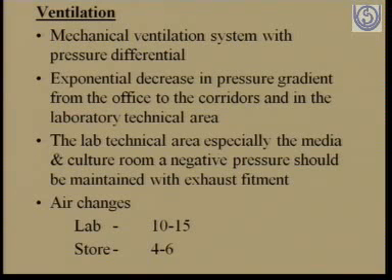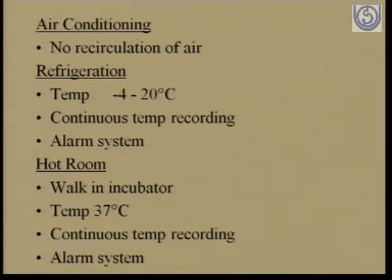Ventilation is a very important requirement because of the nature of the work, especially the microbiology work, where you need a separate air handling unit for the microbiology area so that the possibility of mixing of air can be avoided. Laboratories require approximately 10 to 15 air changes. In the store it can be less. There should not be any recirculation, especially from the microbiology area.